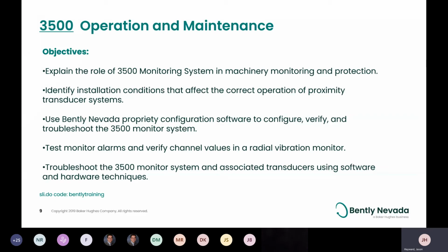Proximity probes are the majority of our piece of the market, so to speak. Proximity probes are really where Bently Nevada started many years ago. When I look at and troubleshoot a 3500 system or a software system like System 1, I like to call the proximity transducer systems the pointy end of the stick. If your transducer systems aren't installed correctly, your monitoring system, your 3500, is not providing you the value that you expect. And then your System 1, your asset management software, has either poor or bad data from a faulty transducer, and the data you're using to analyze vibration issues or machinery condition is not necessarily good based on your transducer system.